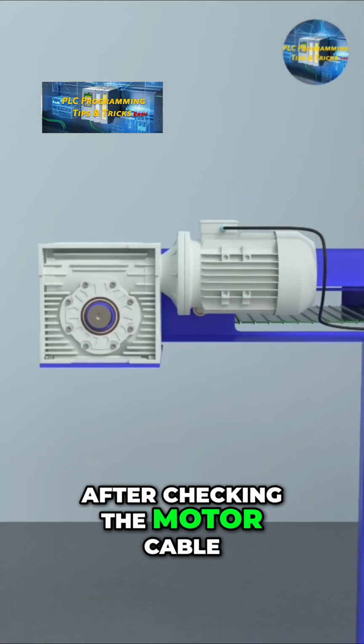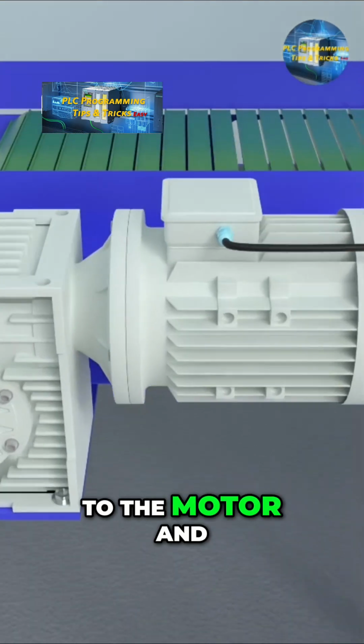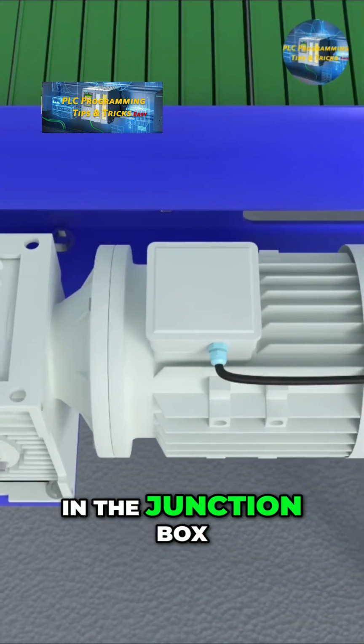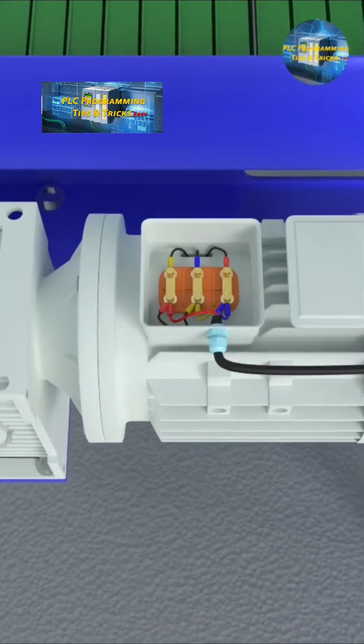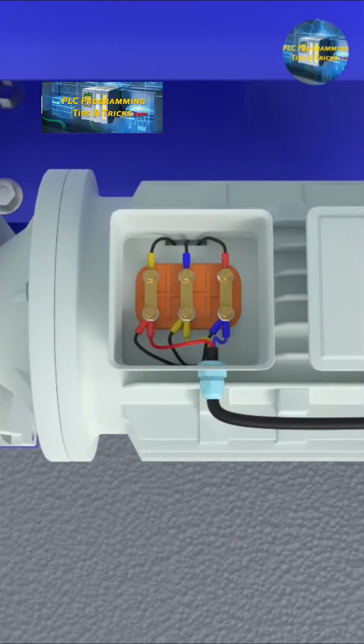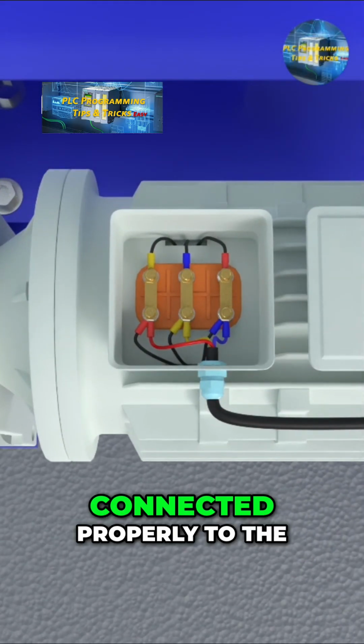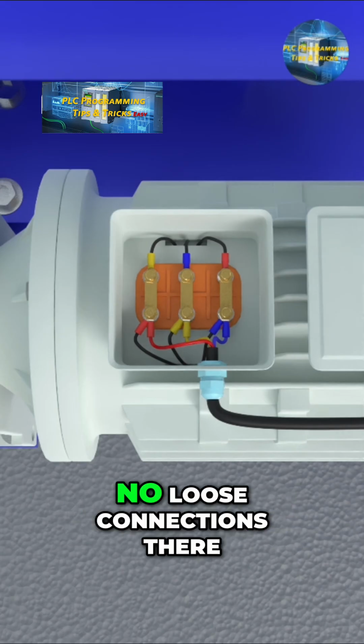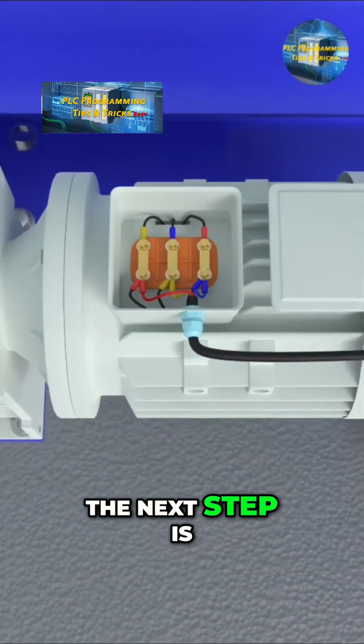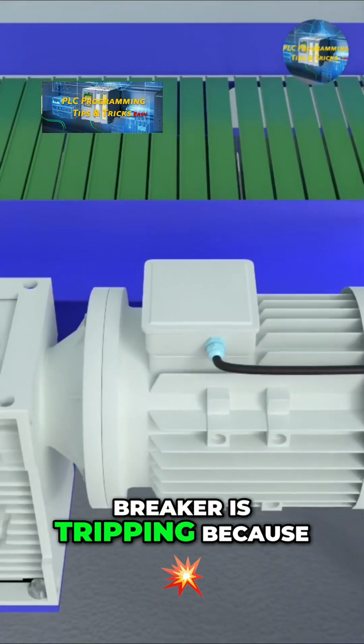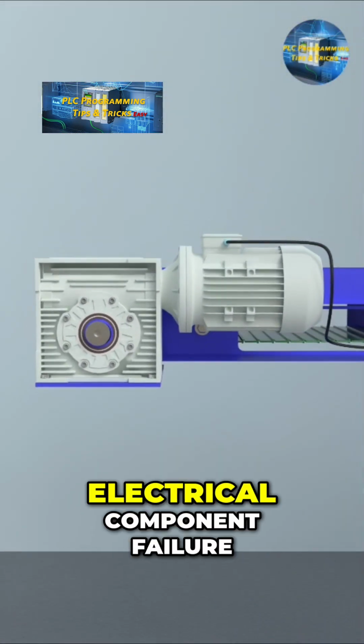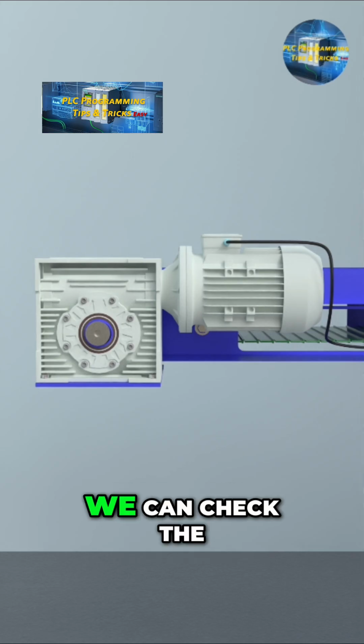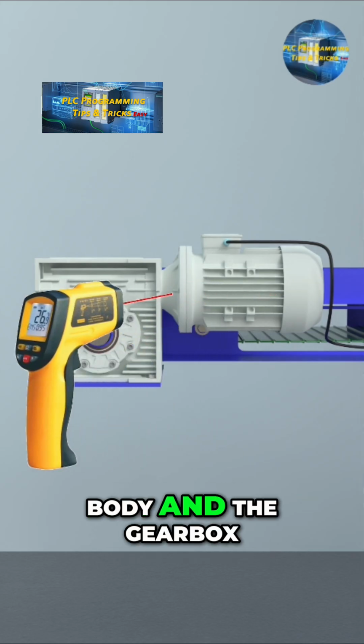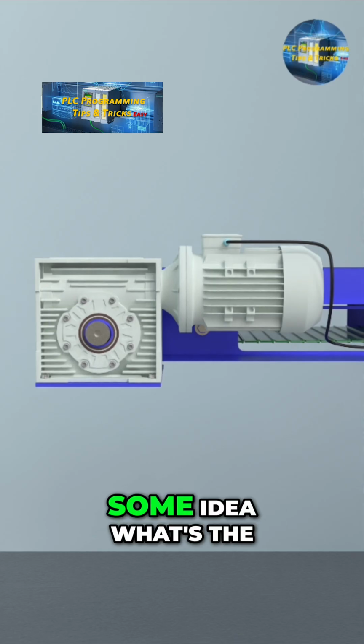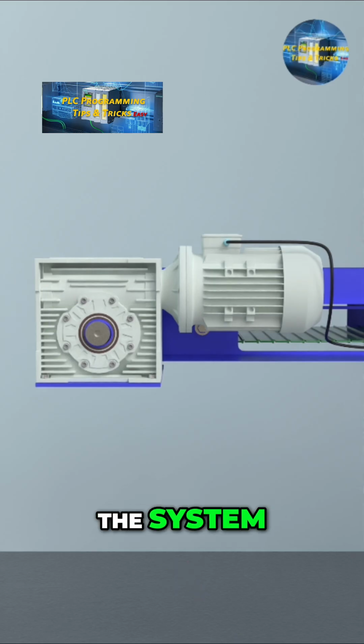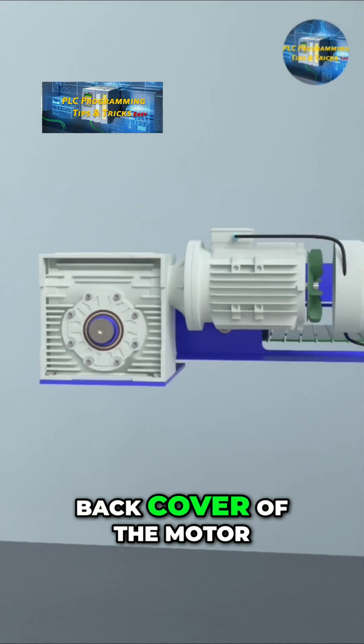After checking the motor cable, next we can go to the motor and check the wire connections in the junction box. If the wires are connected properly to the terminals and there are no loose connections there, the next step is to determine if the breaker is tripping because of a mechanical or electrical component failure. We can check the temperature of the motor body and the gearbox. It will give us some idea what's going wrong with the system. For this, we will open the back cover of the motor.